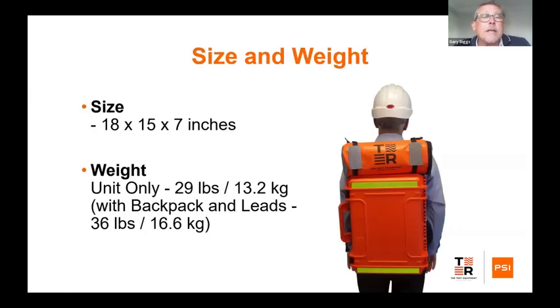As I said, the size is 18 by 15 by 7 inches, and the weight is only 29 pounds, which equates to, actually it's lower than I even said, a mere 13.2 kilograms. With the backpack and leads, which is the roll on the top of the box that holds your lead sets, that will bring it up to still only 16.5 kilograms or 36 pounds. So, much lighter than having a traditional test set on your back.